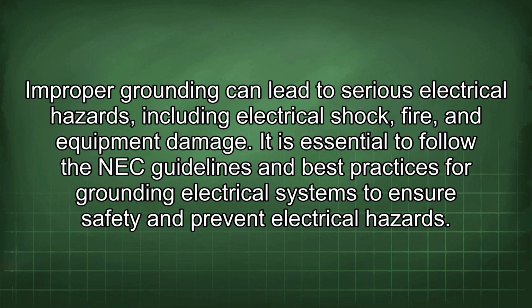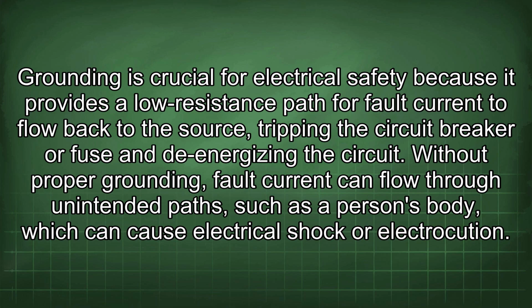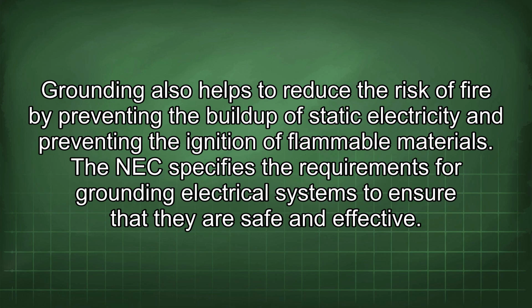Grounding is crucial for electrical safety because it provides a low resistance path for fault current to flow back to the source, tripping the circuit breaker or fuse and de-energizing the circuit. Without proper grounding, fault current can flow through unintended paths such as a person's body, which can cause electrical shock or electrocution. Grounding also helps to reduce the risk of fire by preventing the buildup of static electricity and preventing the ignition of flammable materials.